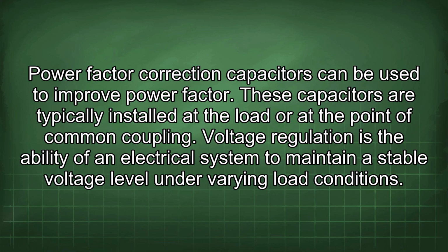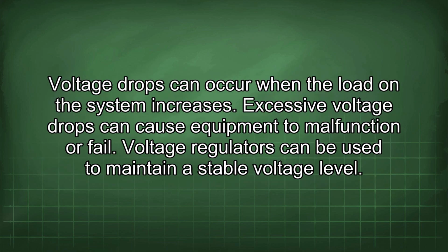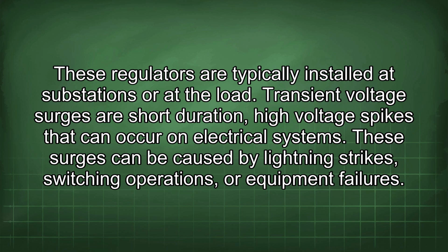Voltage regulation is the ability of an electrical system to maintain a stable voltage level under varying load conditions. Voltage drops can occur when the load in the system increases. Excessive voltage drops can cause equipment to malfunction or fail. Voltage regulators can be used to maintain a stable voltage level. These regulators are typically installed at substations or at the load.